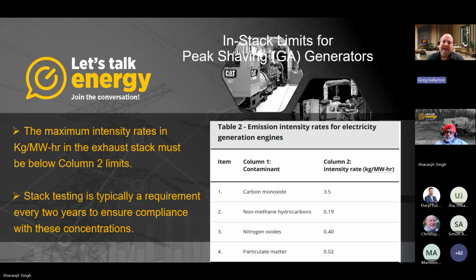That's what that is. And just as a comparison, a standby generator meets the exemption criteria if it's 9.2 grams per kilowatt hour in stack. So this is basically tier 4 criteria. You need an SCR typically to bring the emission levels down to these intensity rates outlined in column 2. One other important thing that I want to bring up is that stack testing is typically a requirement every 2 years to ensure compliance with these concentrations, because we know these generators degrade over time, and we want to make sure that the in-stack limits are always being met.